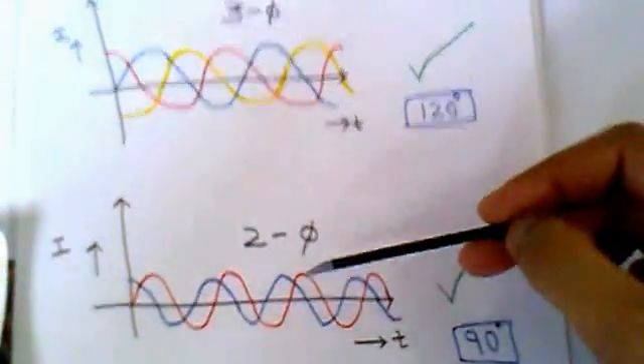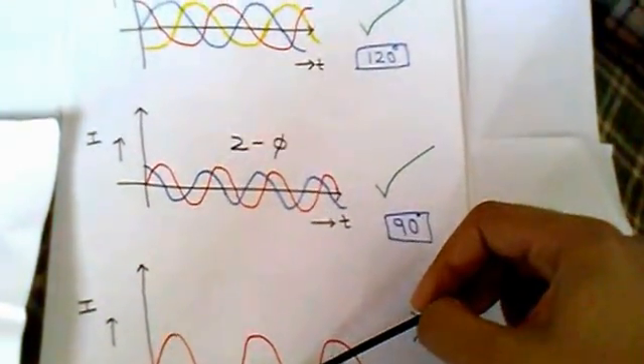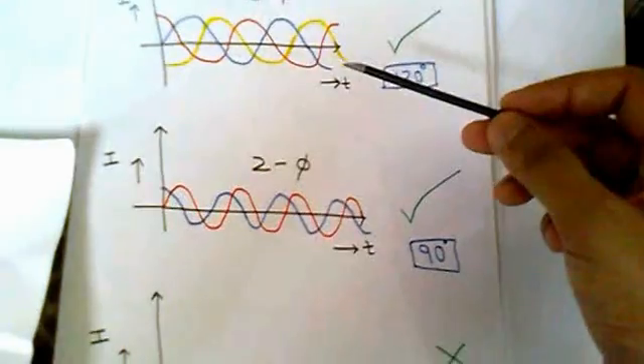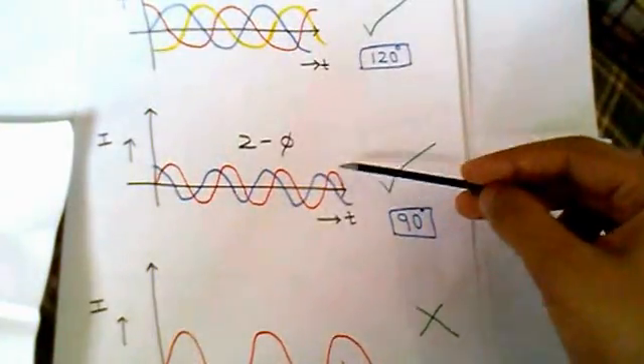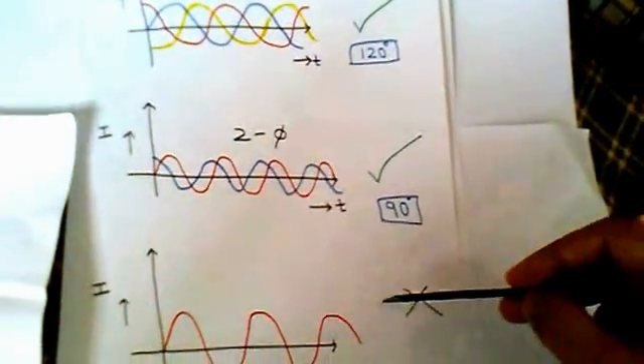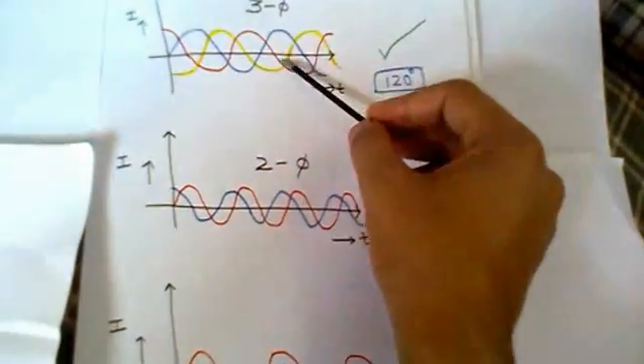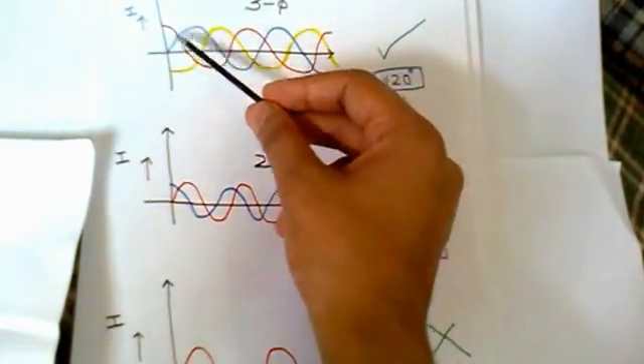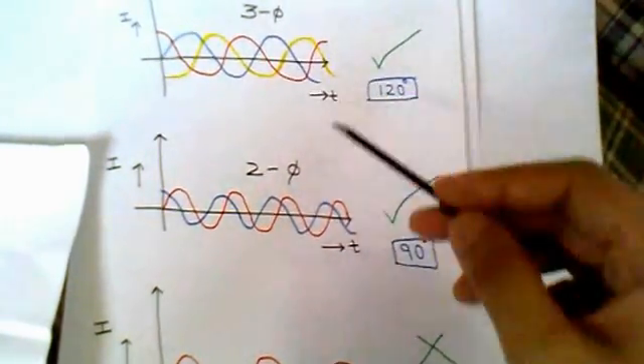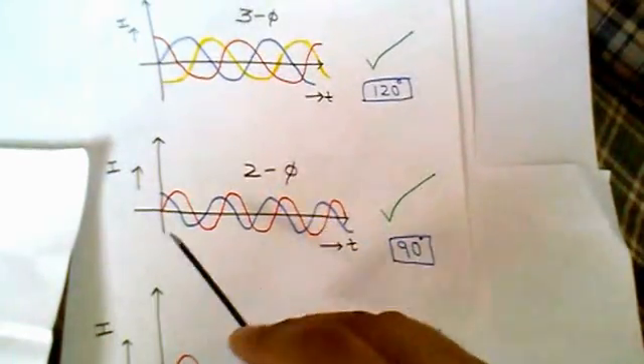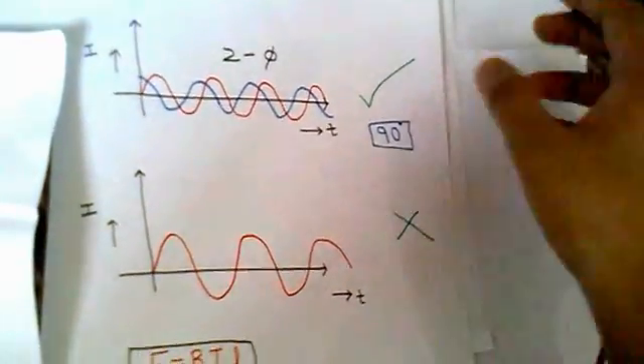These are the three waveforms that I have drawn. This is the three phase waveform, this is the two phase waveform, and this is the single phase waveform. There is a very peculiar thing about three phase and two phase — only these two waves are capable of creating a rotating magnetic field, whereas a single phase cannot. In the three phase, these three currents painted with yellow, blue, and red color are all displaced by 120 degrees with each other. Whereas in case of two phase, the currents are displaced by 90 degrees. A single phase cannot create a rotating magnetic field.